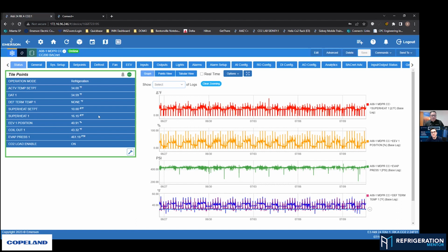There's a lot of moving pieces. If I've got an issue with case A, I'll move to case B -- alright, that one's good, everything's going to run there. We move on to C, then come back to A and fix that thing and restart that action. Because we have direct communication to the case, it's a lot easier to narrow it down -- you've got an EEV, a stepper or pulse valve, so I can directly close that valve at the case and just deal with that case on its own.